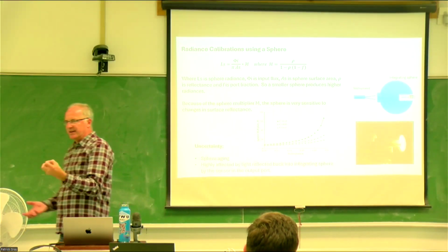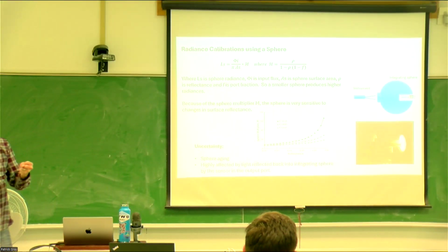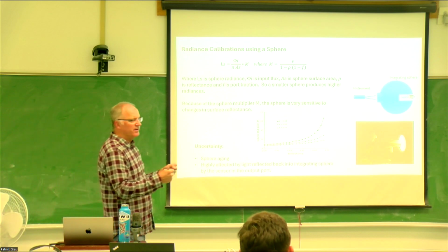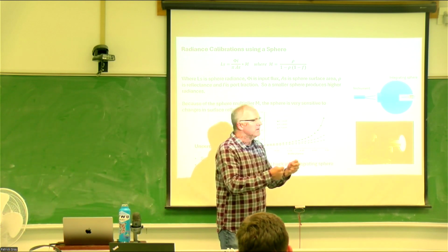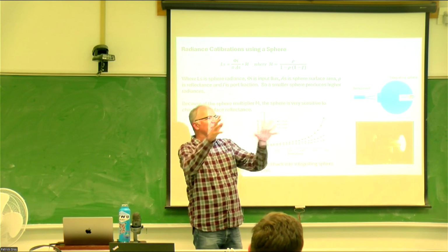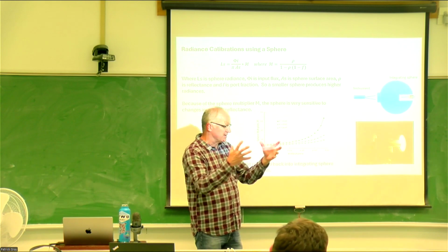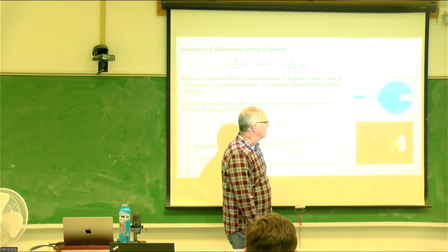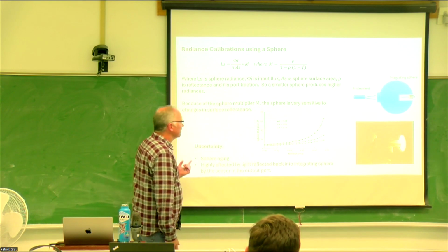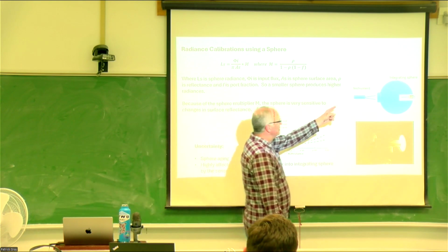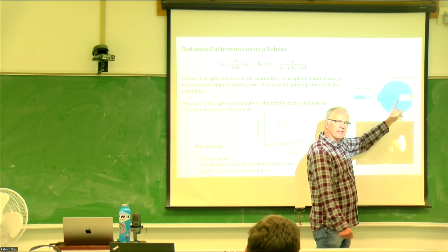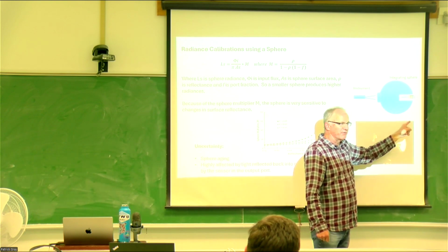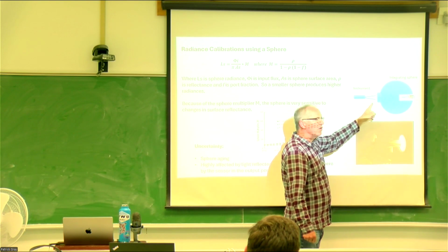We've got holes in it where there's no Spectralon. So we have to account for those holes because that could change how Lambertian and how equal the light actually is inside of that sphere. And that's important because you don't insert your instrument inside, you slide it through the opening and put it at some small distance away.